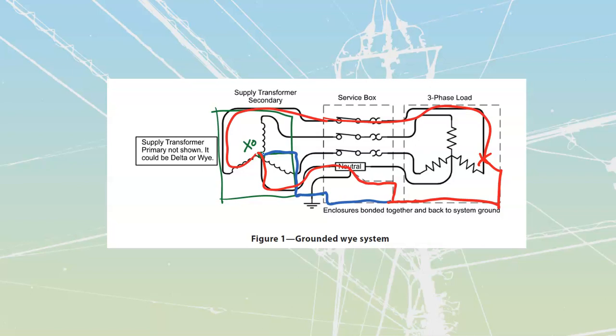And ultimately, that's what we're really looking for. We need to have predictability on these. So you do have to remove one of these two. If you're going to ground it over here at the service neutral, you have to remove that one there that comes as part of the transformer. Alternatively, if you're not going to ground at the service neutral, but you want to ground at the transformer itself, then you would have to leave this one in, and you'd have to make sure that all the rest of your bonding is tied together so that we've got a path for my current all the way back through. Just draw that in as being grounded right over here. Okay, you can complete your self-test and on to the next one.